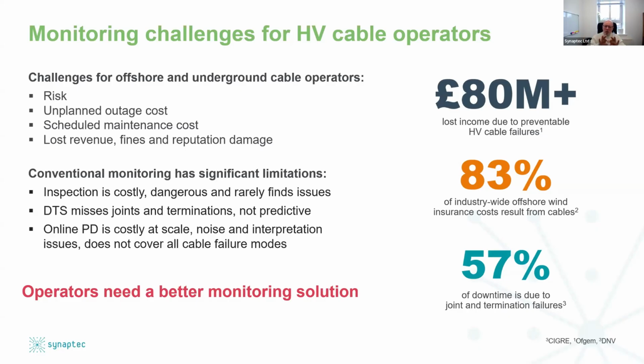And unfortunately, all of the conventional instrumentation, like distributed temperature sensing or DAS, that's looking at the structural integrity of the cable, so it misses the joints and terminations. When you try to do manual inspections, sometimes you can't see at an electrical level what's going wrong, and it's a bit of a superficial task, and you don't actually get ahead of or identify problems as they're starting to occur. So there's a challenge and a limitation with conventional monitoring that says we're either looking in the wrong place, or we're not seeing it early enough, or the results are ambiguous.